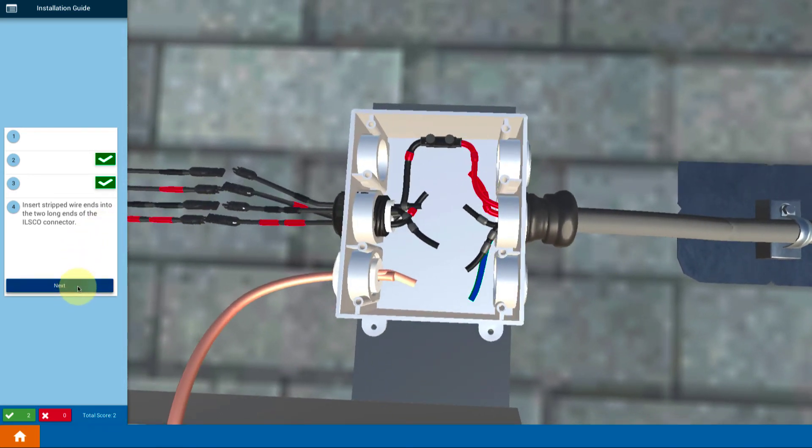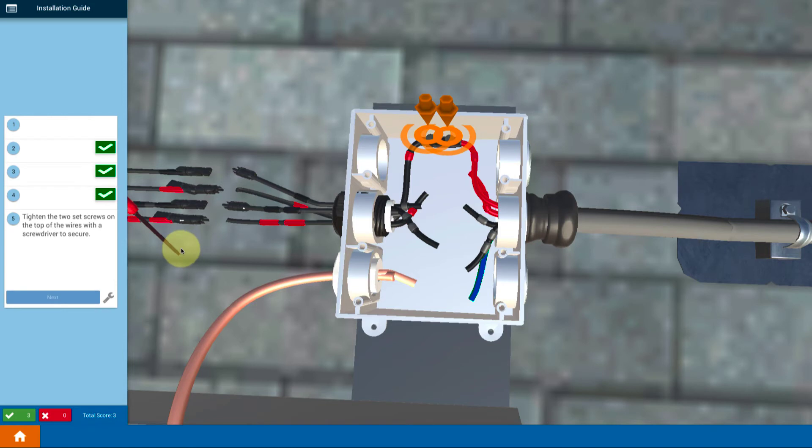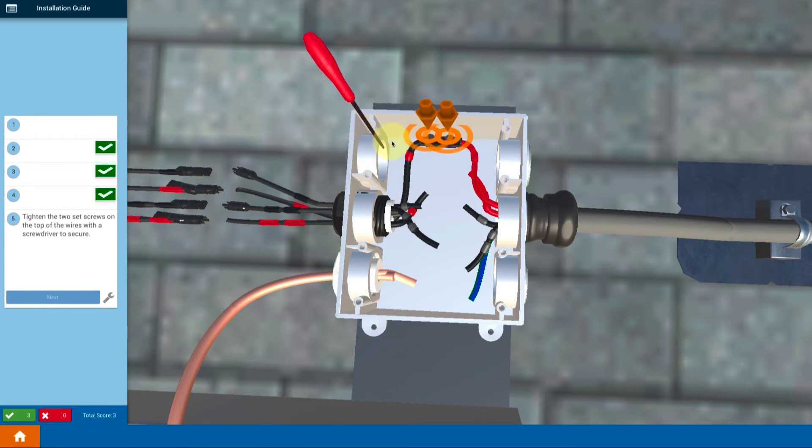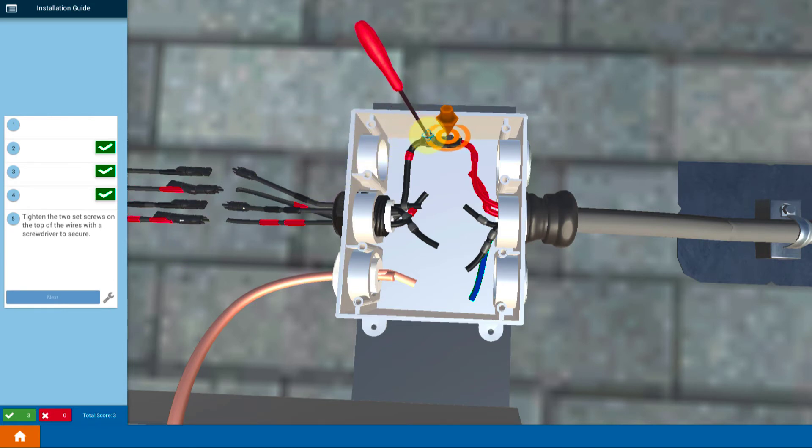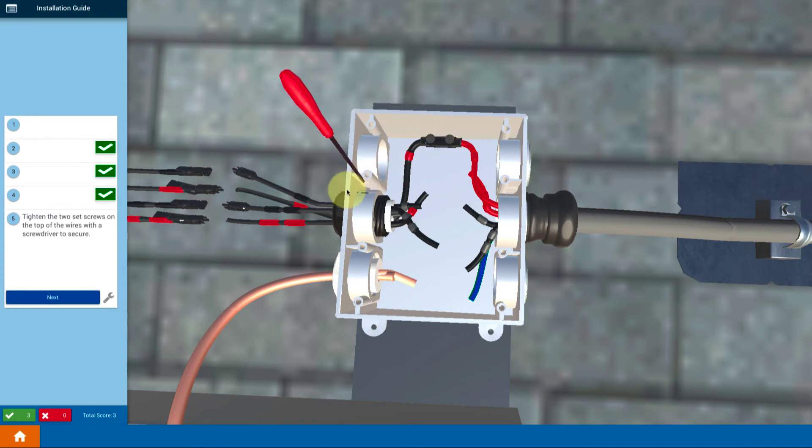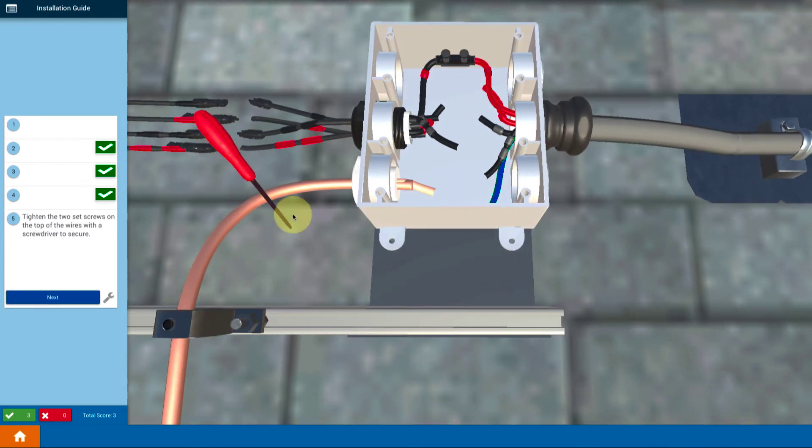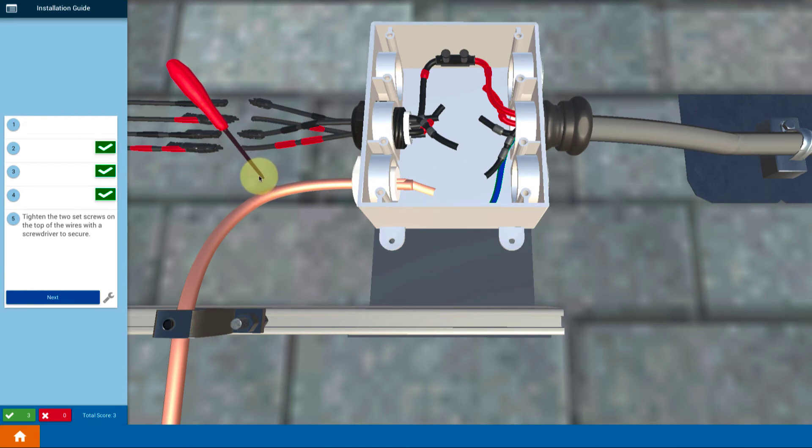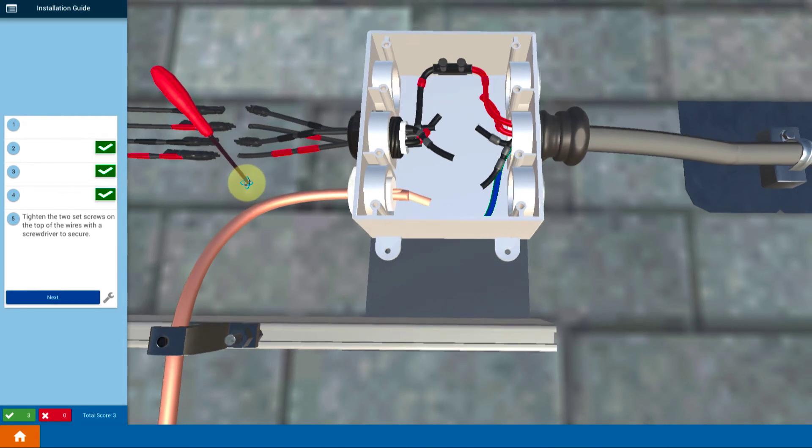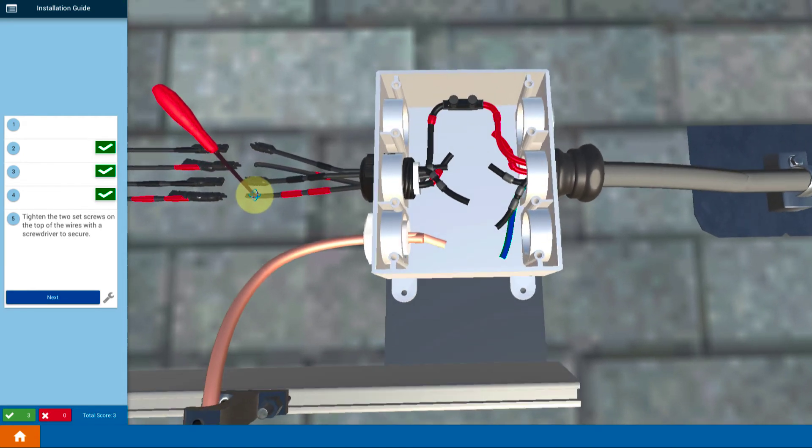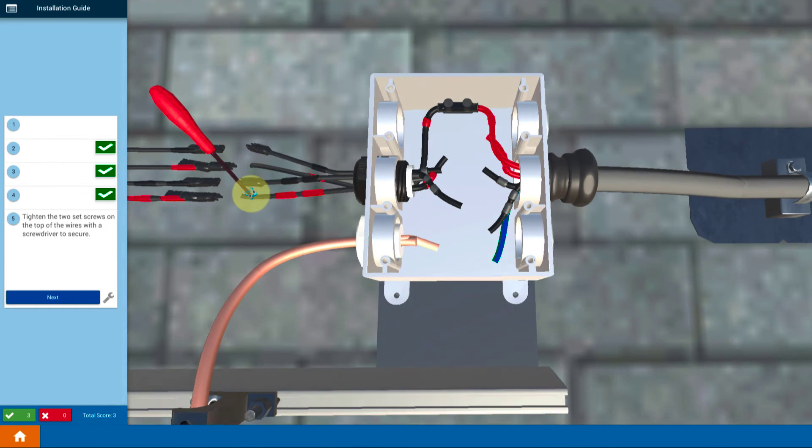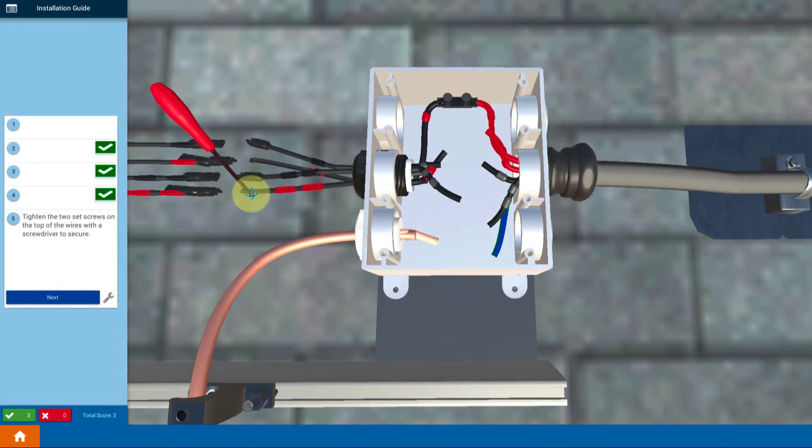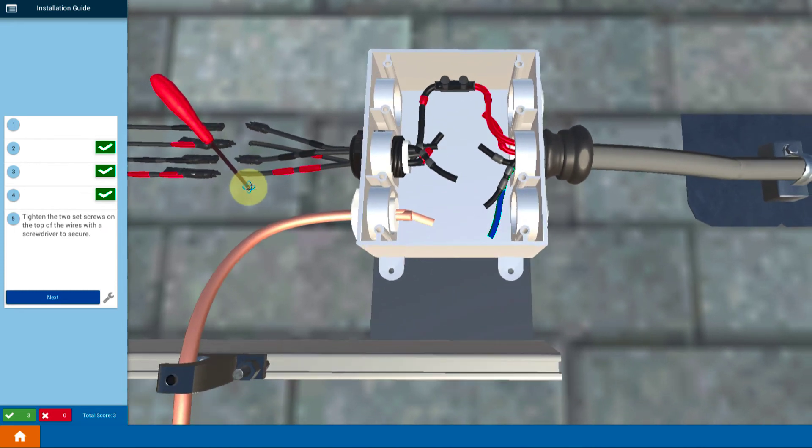And then the way that you make the solid connection is to use a screwdriver and put down a set screw that strongly connects onto the wires inside of the connector. It's a mechanical connection. It's not a screw type of connector or twist on. It uses set screws. Very strong and very positive.